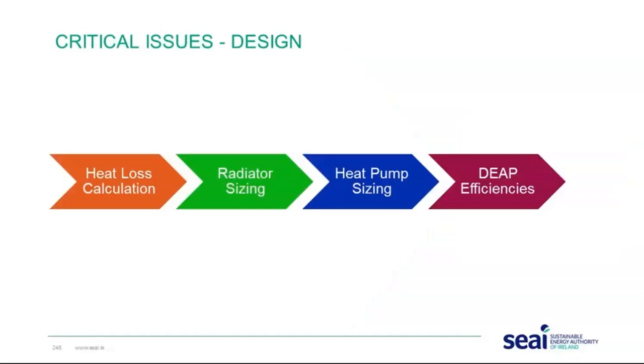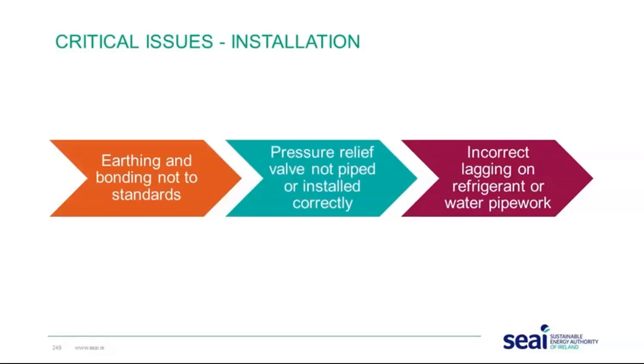The heat loss calculation must be carried out during the design stage. The heat emitters must be sized correctly, or the sizing of existing radiators must be verified. The heat pump unit must be appropriately sized, and the design efficiencies must be met. Then on the installation, earthing and bonding must comply with the electrical standards. You need to check that the pressure relief valve is piped and installed correctly, and that all pipework in unheated spaces has the correct lagging.